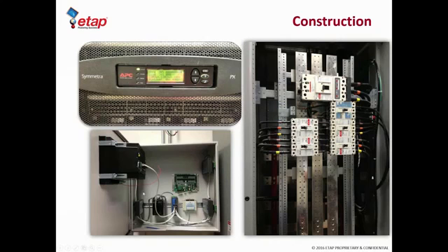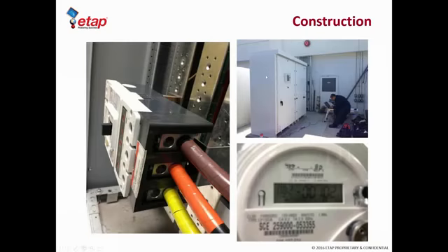The communications were essentially set up as well for each of the incomers from the utility, from the inverter itself. And then we also installed branch circuit monitoring for some of the loads that we wanted to measure in a little bit more detail, especially the HVAC units. We also put metering onto the UPS, which serves the data center that we run within the facility, as well as the critical computers, especially for the developers that are working very hard on the ETAP software.